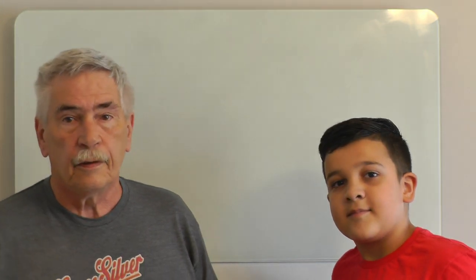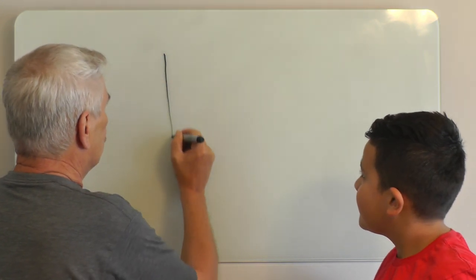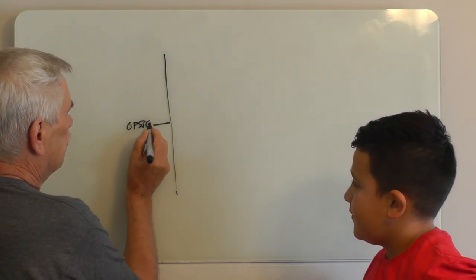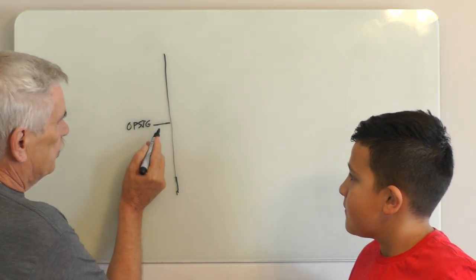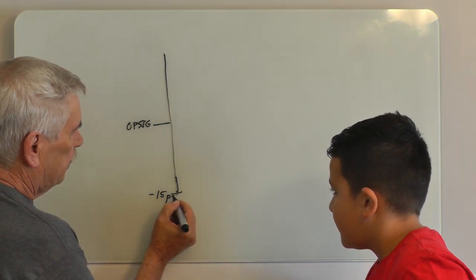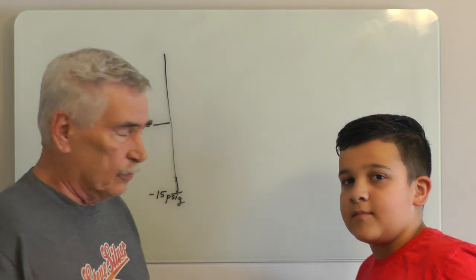Since we're talking about pressure, let's go over that a little bit. Let's talk about gauge pressure. I'm going to draw a line and call this zero PSIG — pounds per square inch gauge. Anything below this line is going to be a vacuum, so down here we'll call this minus 15 PSIG. Atmospheric pressure is about 14.7 PSI at sea level, but for our math and a lot of these transducers, especially absolute pressure transducers, they're calibrated to use minus 15 PSIG, or zero PSIA — absolute pressure.